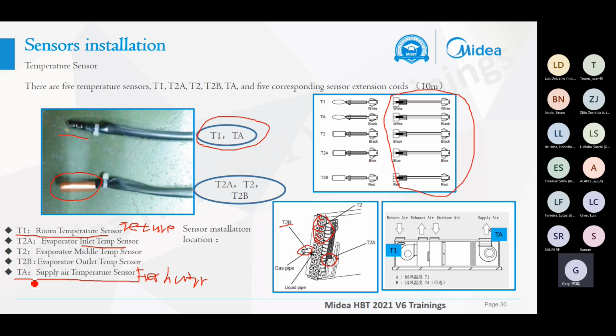And for the T1 and TA, if you select return air control, you can put the TA in the return air port. If you select fresh air control, or what we call circular air control, you should put the TA sensor in the circular air. You can also put all the sensors in their places and select whether to use TA control or T1 control via the wire controller or the dial switch. You can place all the sensors in the AHU directly, and then select by the dial switch.